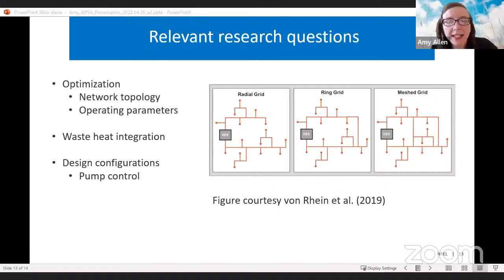In the case studies I mentioned previously, which were oriented around this network topology optimization problem, I didn't see the holy grail of benefits from greater grid connectivity offsetting the higher cost associated with the network. But that's also to some extent an artifact of the grid configuration considered, with parallel connections of buildings to the loop, which limits the extent to which buildings see a different supply temperature resulting from loads connected at a different place in the network. It's possible that with a series network configuration in a one-pipe layout, those benefits would offset the additional cost associated with the mesh network.